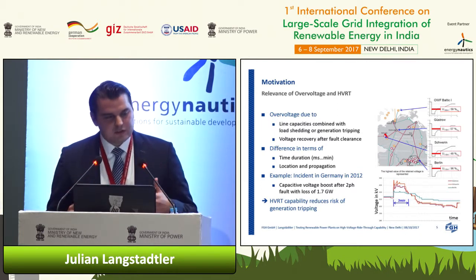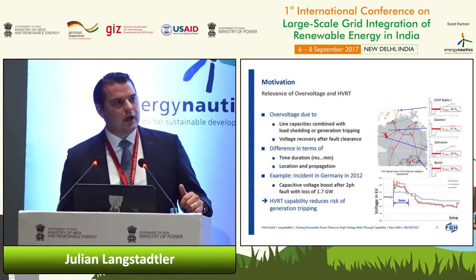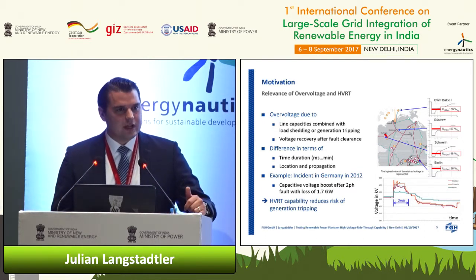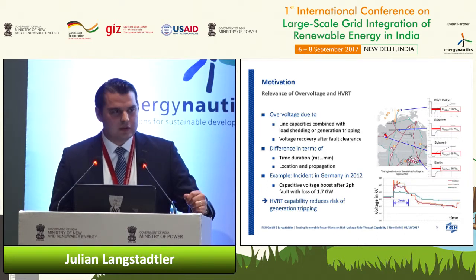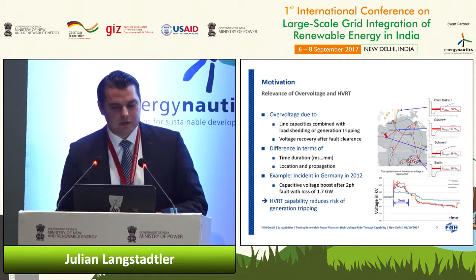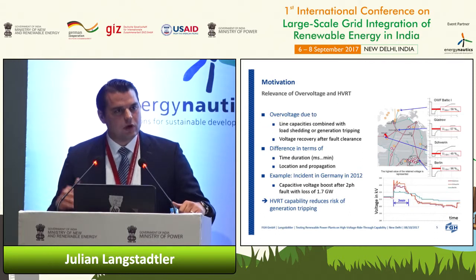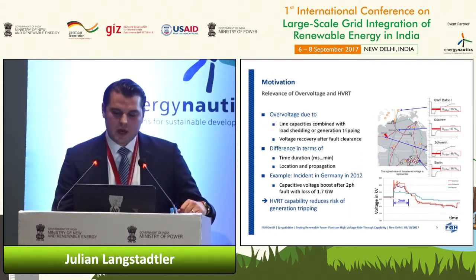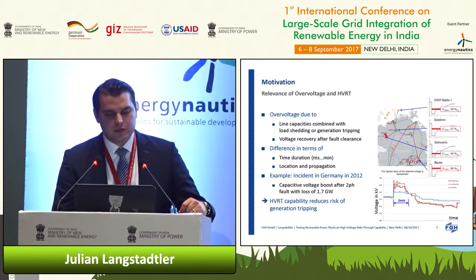However, in this system also, a lot of wind turbines are already erected that are not LVRT compliant. So during this period, it was in winter, there was a lot of wind, and most of the wind turbines were operating. And after the fault occurred, a significant amount of the wind turbines tripped. However, after the tripping, because of open unloaded transmission lines, we had a very strong voltage boost in the system itself. And this led to further tripping of wind turbines.